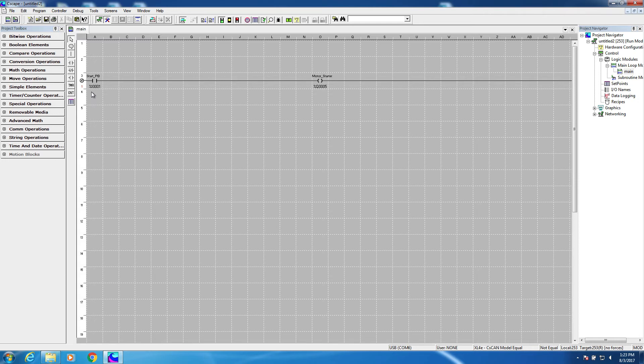The obvious problem with this circuit is that as soon as I let go of the start push button, the motor starter stops. So this is where we need to insert what's called a seal circuit, another basic element of ladder logic. To do that, we're going to put a set of parallel contacts around the start push button using the branch tool.